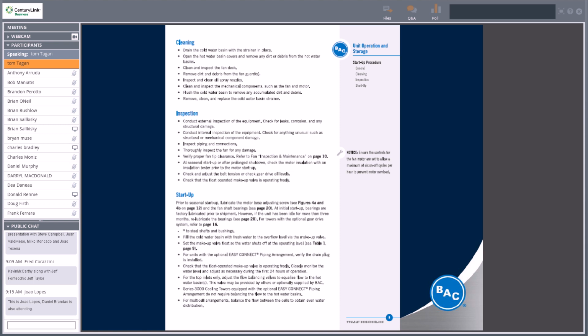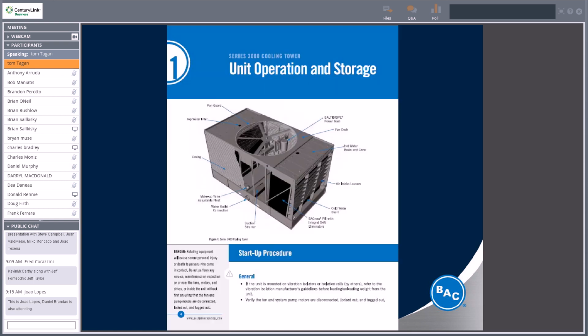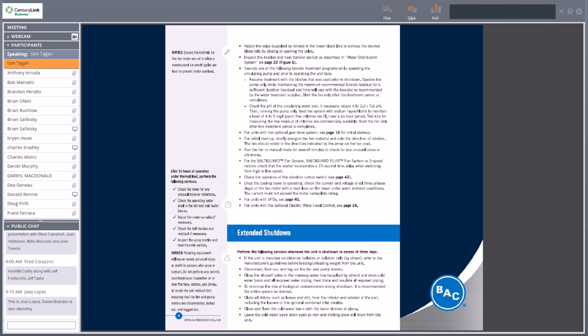Startup, a little bit later on in the O&M, it goes into some shutdown and seasonal if you do have a cooling tower that you shut down for the winter, and what to do to put it up for the winter and then get it going again. Generally, my presentation that I'm going through today is what I would do if I was on site with you during an initial startup or training. Again, a lot of the information that you need to be aware of is detailed in the O&Ms. So again, looks like I've got some duplicate slides here.